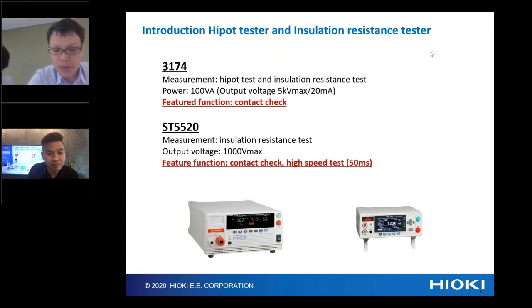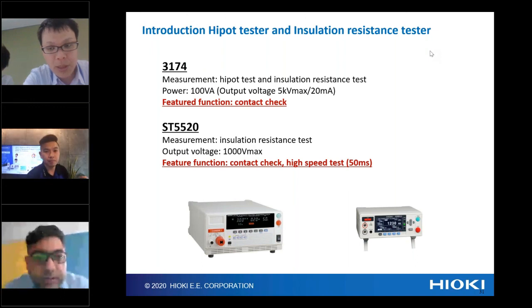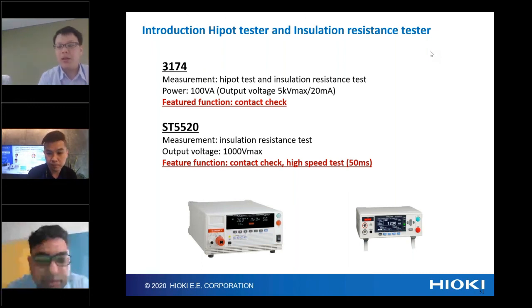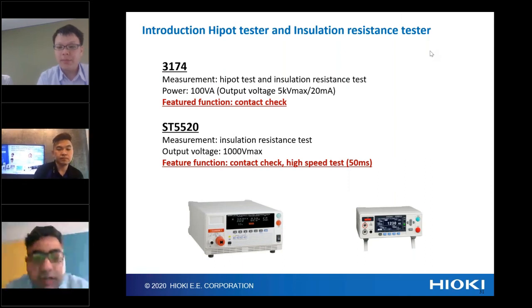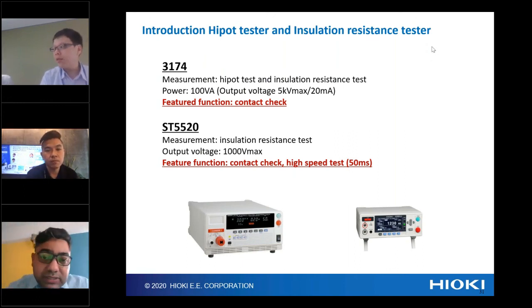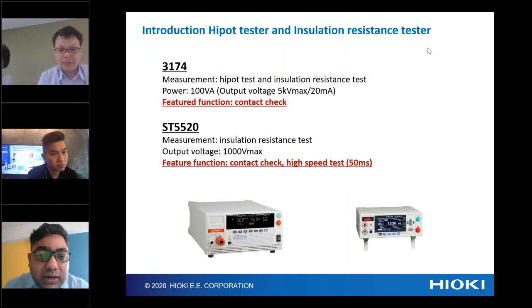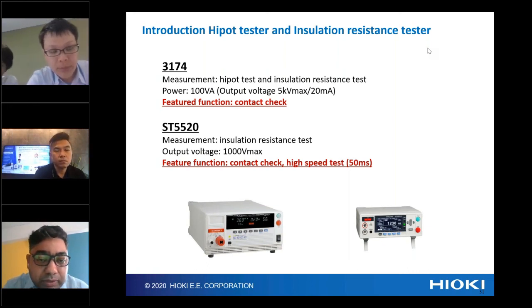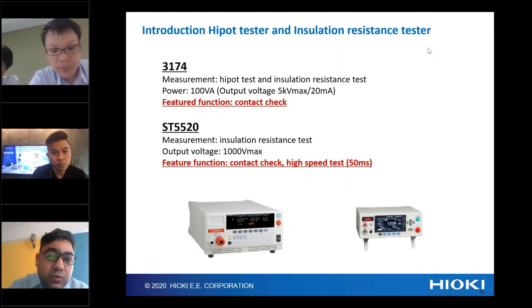Okay, the frequency of the leakage current test. It depends on the usage of the machine. We can categorize: medical machines start from the X-ray machines and go up to high-end machines like the MRI and the CT scan machines. As compared to CT scan and MRI machines, X-ray machines are used very regularly. So the X-ray machines need very regular testing for the leakage current, right? The users or the manufacturers who are manufacturing X-ray machines do very continuous testing as compared to CT scan and MRI. So it depends on the machine usage.